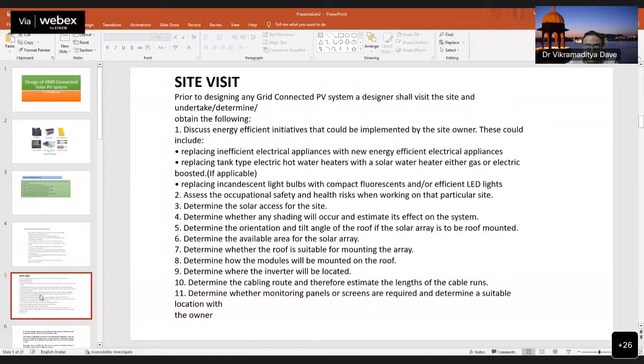ठीक है, सोलर हर पैनल का भी अपना एक वेट होता है 15 से 20 किलो के बीच में. तो ऐसे मान लो आपके 100 पैनल लग रहे हैं, तो total the weight you are putting on this is 15 into 100, means 1500 kg weight is put on it. So if your rooftop is very old or made up of some old material, then it may cause a crush in the whole building. So try to avoid such type of building and suggest them that since it is an old building, it is very difficult to install the panel on it.